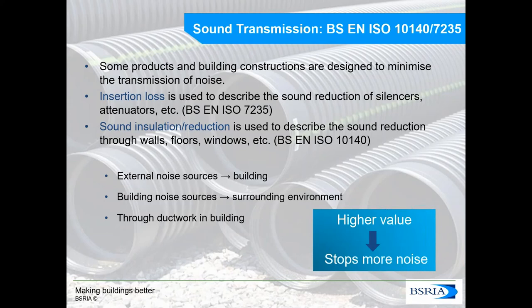The third type of acoustic measurement is sound transmission. There are two types of descriptors: insertion loss, which describes the sound reduction of silencers and attenuators, and sound insulation or sound reduction, used for walls, floors, windows, and building fabric. Three transmission aspects are commonly considered: external noise sources such as traffic being transmitted into a building, building noise sources being transmitted to the surrounding environment, and noise transmitted through ductwork within buildings.